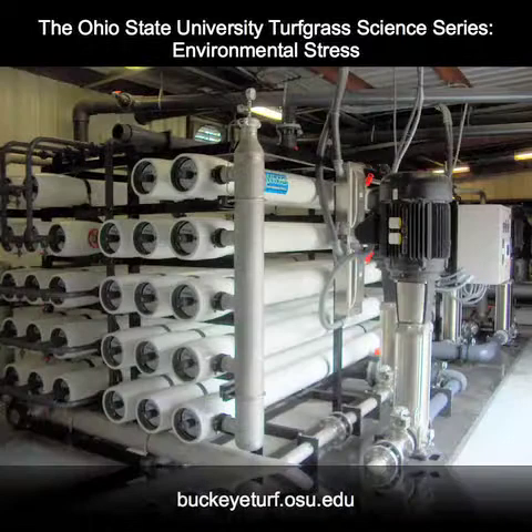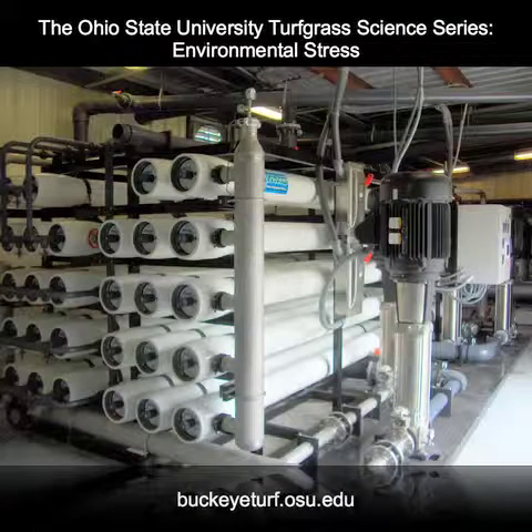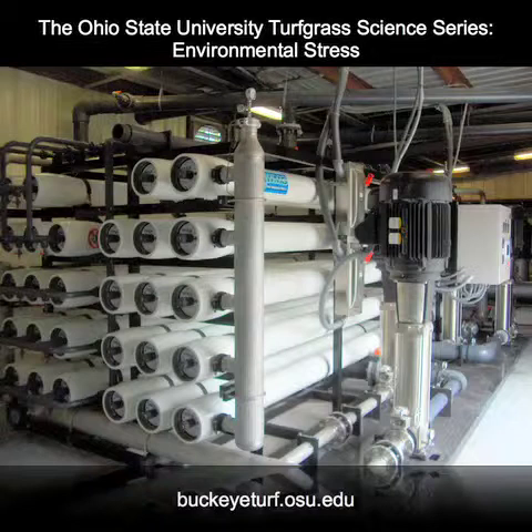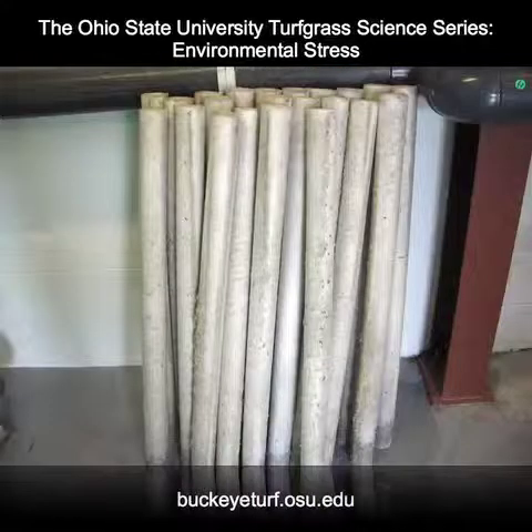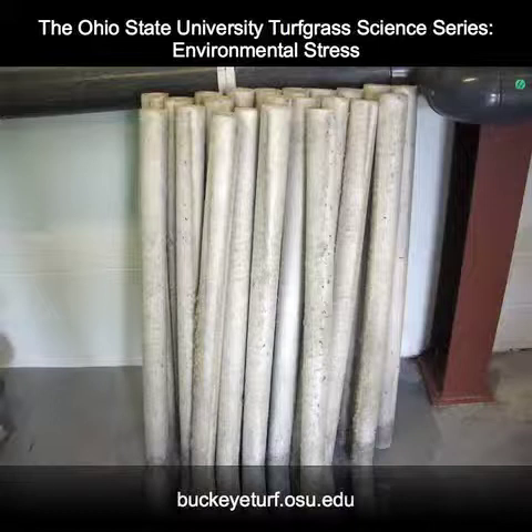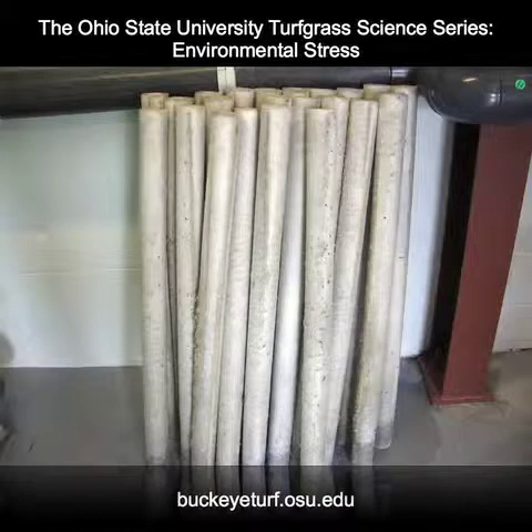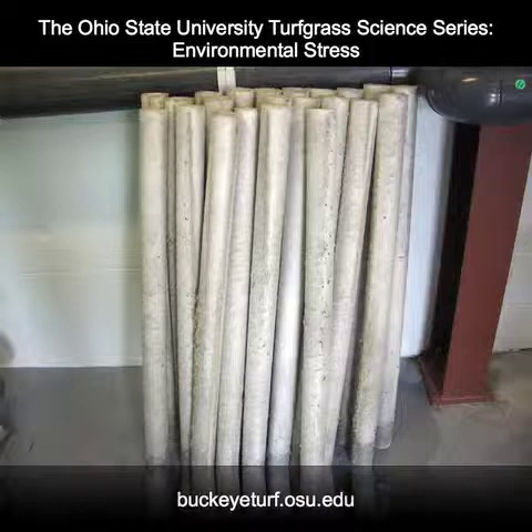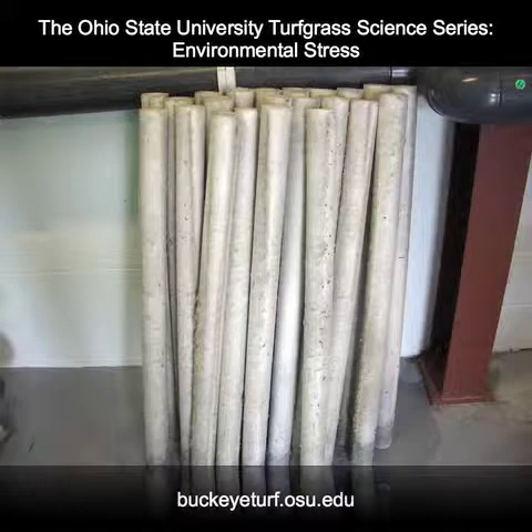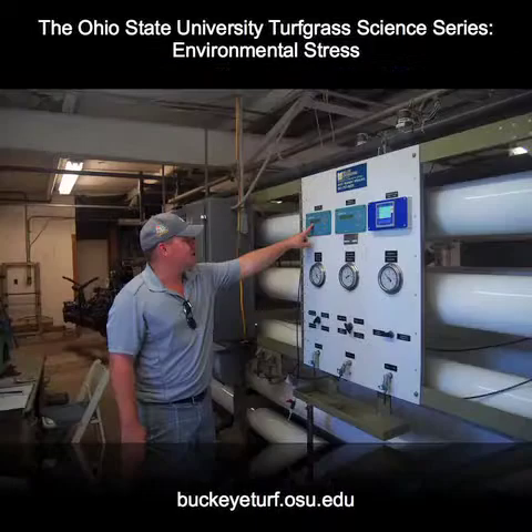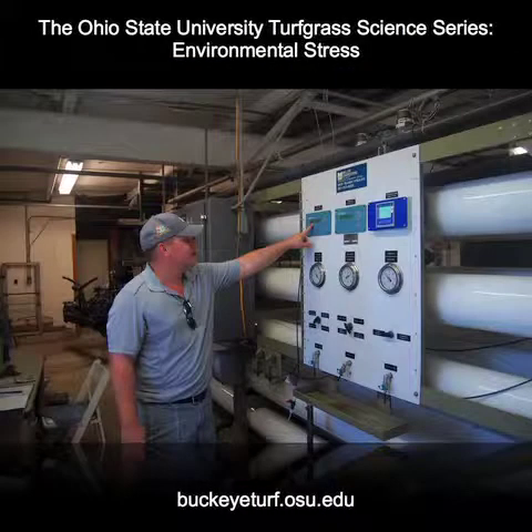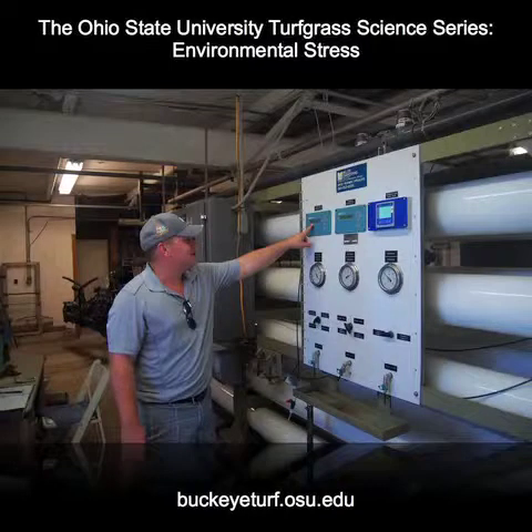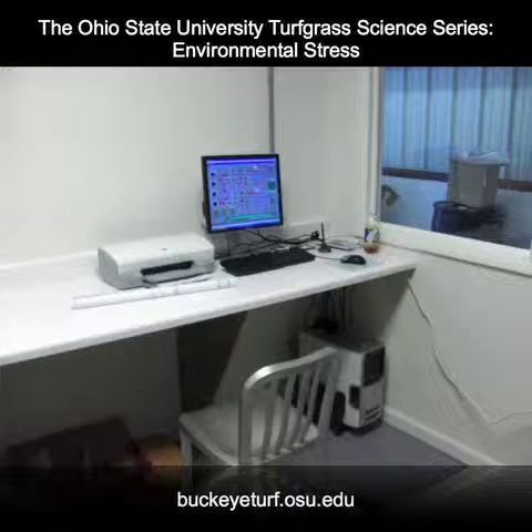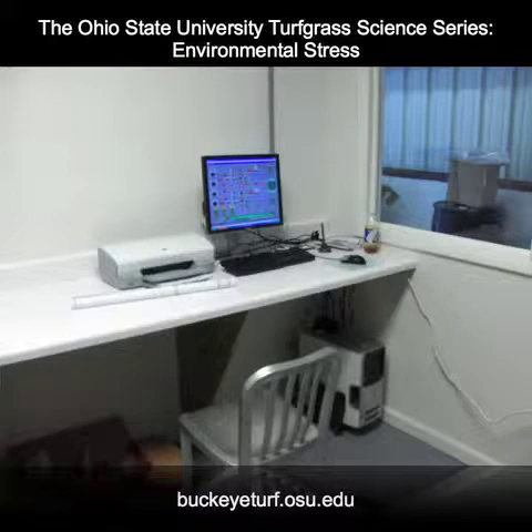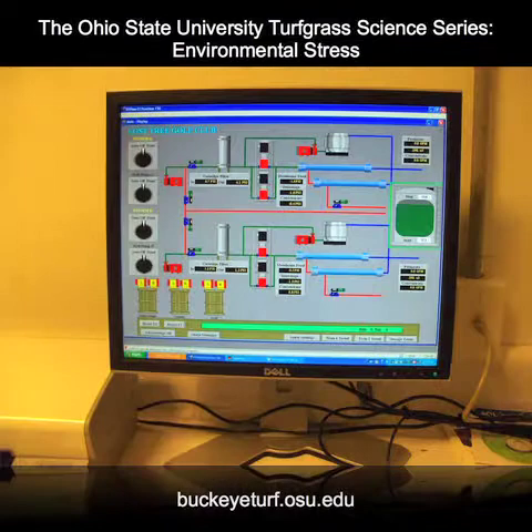The actual removal of the salt from the water takes place in these 20-foot long tubes. The tubes contain membranes where the salt is separated from the water. It takes considerable pressure, thus energy, to force the water through these membranes. This process is known as reverse osmosis. As the water moves through the membranes, the purity of the water can be determined, for example, using electrical conductivity measurements. The entire system, from bringing the salt water into the facility till it is discharged, is monitored.